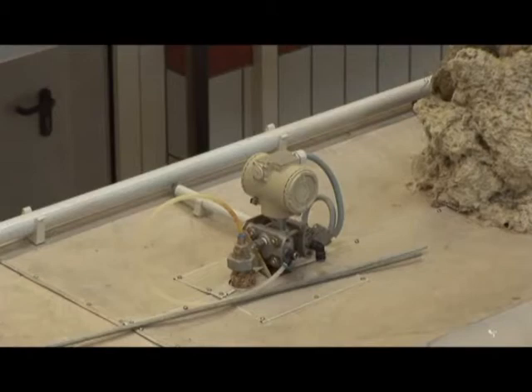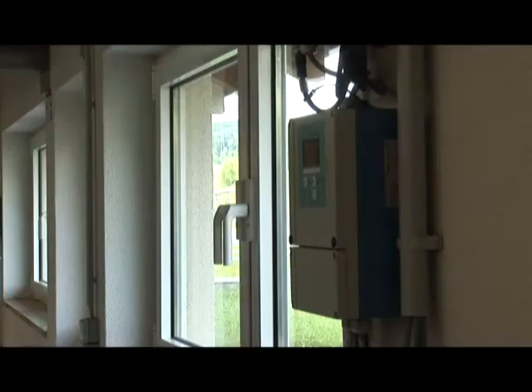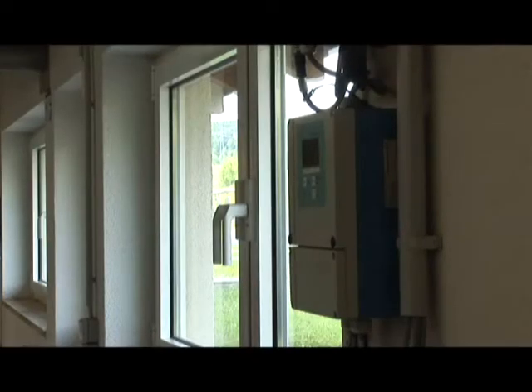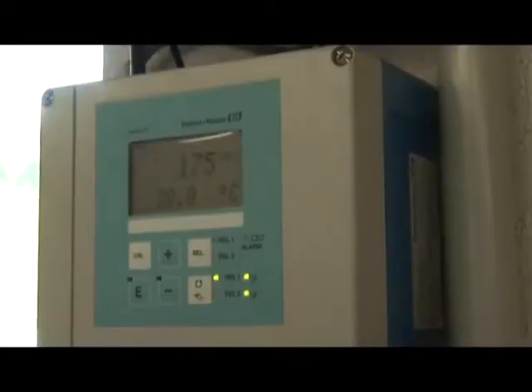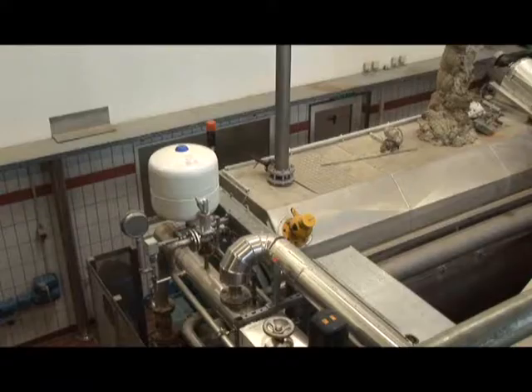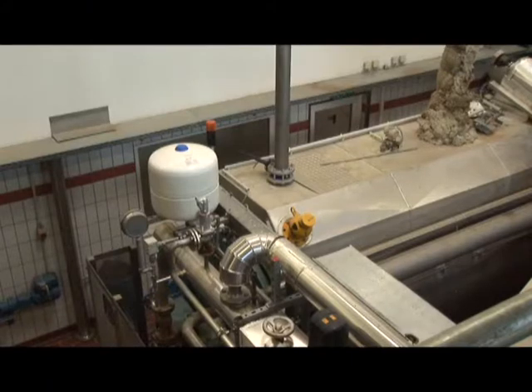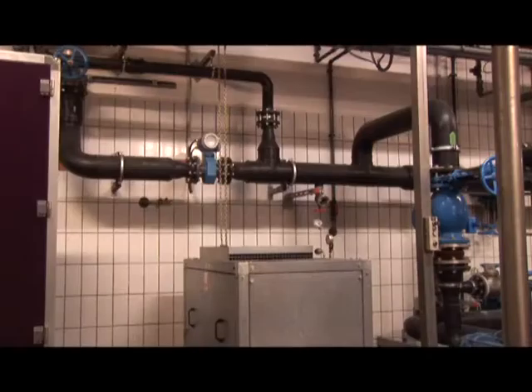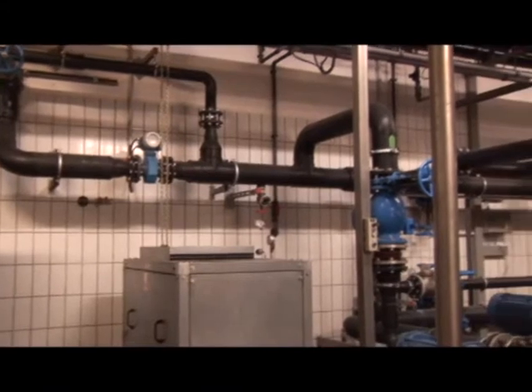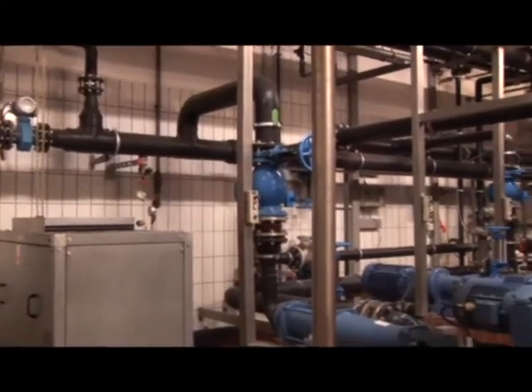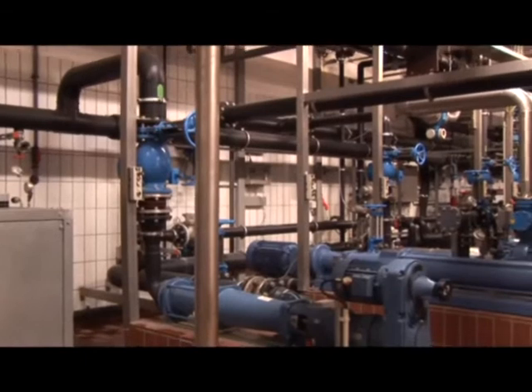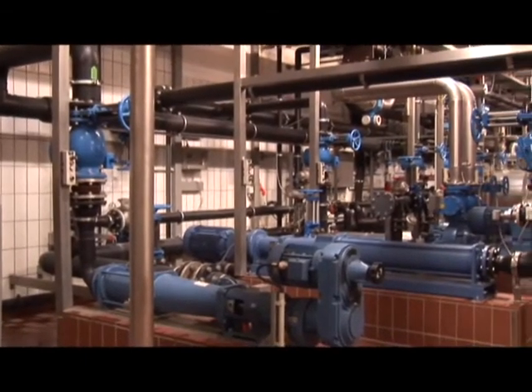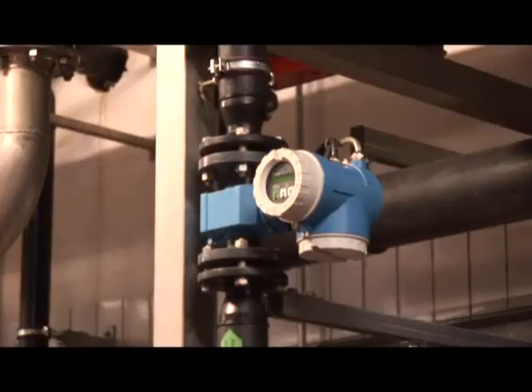The measurement ensures that no flammable gas mixture can be established in the dryer. The oxygen sensor is supplied and assessed by a Liquisys M transmitter in a separate unit. Pressure measurement at the inlet is protected against the heat by a siphon. All media, from sludge to cleared water, is pumped to the relevant containers in the central pumping station. The complete area is monitored by a Promag W EMF and is completely automated.